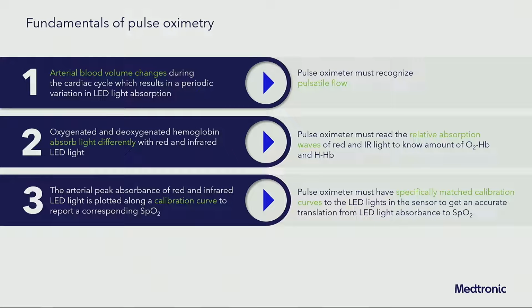It just came out in like December. And it talks about differences in skin tone and the performance of the pulse oximeter, but it also talks about differences in perfusion and the performance of the pulse oximeter. What's really important to take away is that perfusion influences the accuracy of the pulse oximeter. It has everything to do with the fact that the pulse oximeter has to detect these changes in pulsation. So if your perfusion is poor, the pulsations will be dampened, and the pulse oximeter is not going to work.